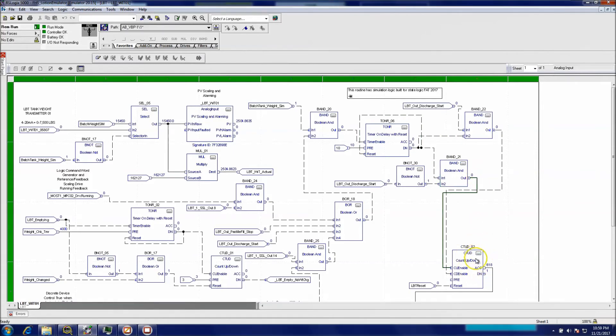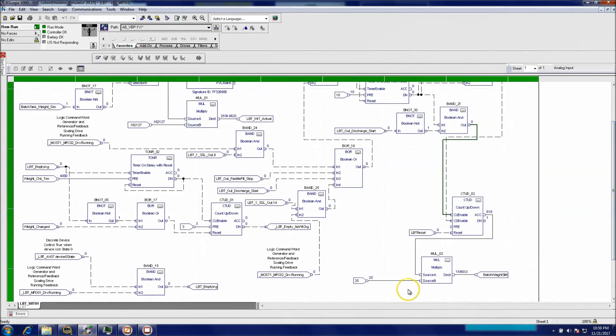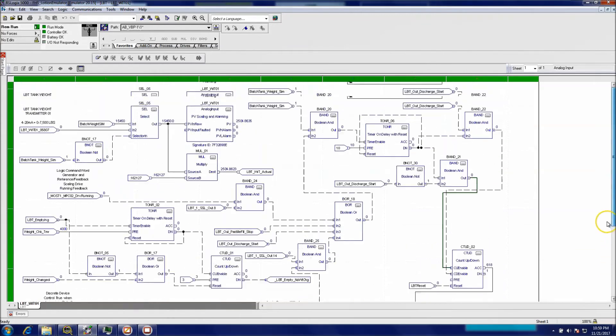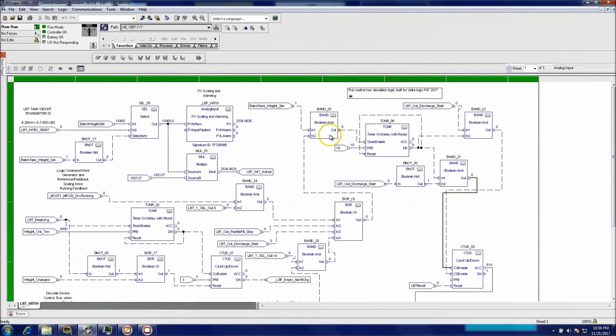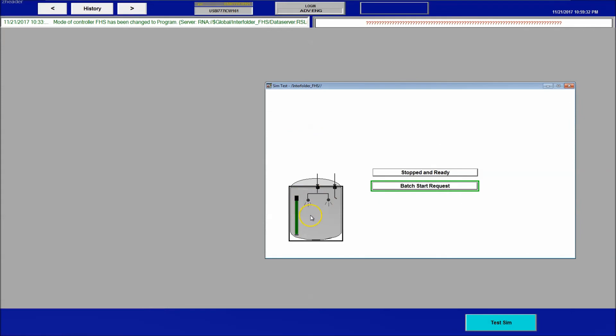It was pretty simple — just: if this and this, let a timer come on; every time the timer times out, index one down to my counter; when my counter indexes up it multiplies by 25, and that's my batch weight. At the current state it's not moving — it's in a stop state because there's a mixing time portion of the process I'm not showing right now. Basically it's hit its fill point and it's actually mixing right now, and after that it's going to start discharging.